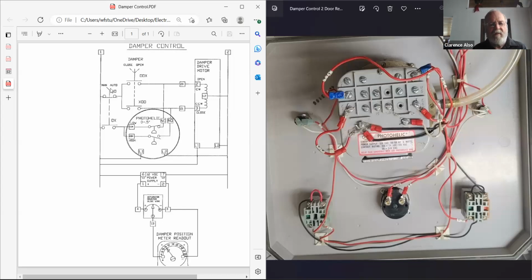Anyhow, so now we're looking at some of the switches we had on the front. We've got the manual-auto here, and we've got the open-close. So here's the manual-auto, first of all it gets its 110 volts, it's going to choose if you're going automatic or manual. This is an or thing, you're either in this position or this position, either the photohelic switches take over or your open-close switches take over. And what are we taking over? We're taking over the open-close windings right here. And when these open-close windings move, so does this pot, and when that pot moves, so does that indicator on the damper thing there.